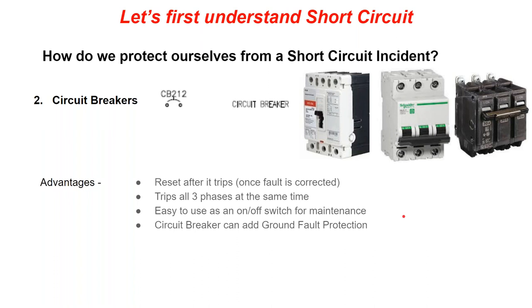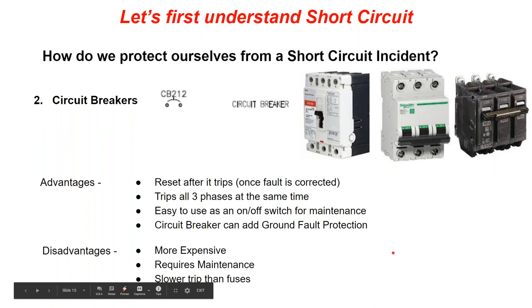Circuit breakers have some advantages over fuses: you can reset after a trip once the fault is corrected, they trip all three phases simultaneously, they're easy to use as an on/off switch for maintenance, and they can add ground fault protection. The disadvantages are that they're more expensive, require maintenance over time, and they're slower to trip than fuses.